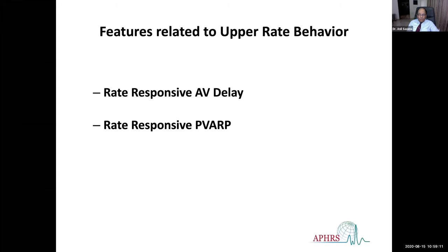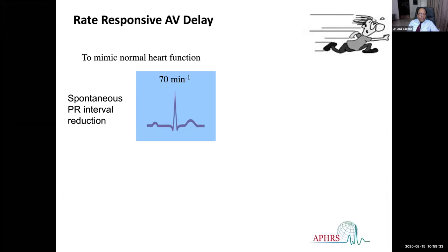So we have to somehow decrease these AV delays. Now, it may not be possible to reduce AV delay all the time, and if we reduce the PVARP too much, there may be other problems. So now, in almost all pacemakers, we have a function called rate responsive AV delay, where the AV delay becomes shorter as the heart rate increases.